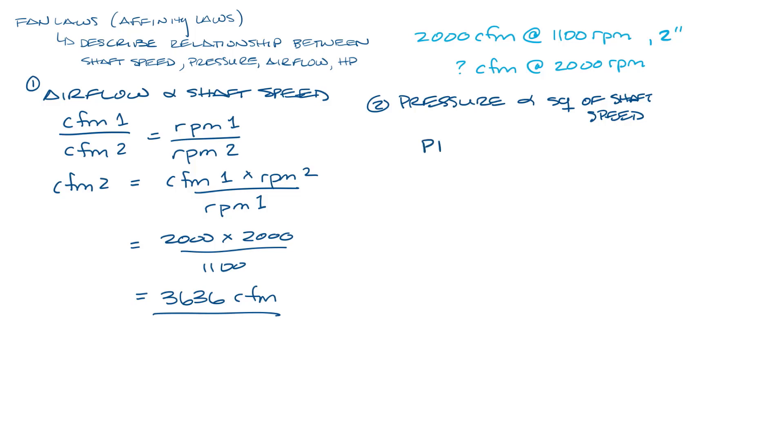So pressure 1 divided by pressure 2 equals RPM1 squared divided by RPM2 squared. So to find the pressure at 2000 RPM, we get the equation pressure 2 equals pressure 1 times RPM2 squared divided by RPM1 squared. And then that comes out to about 6.6 inches.